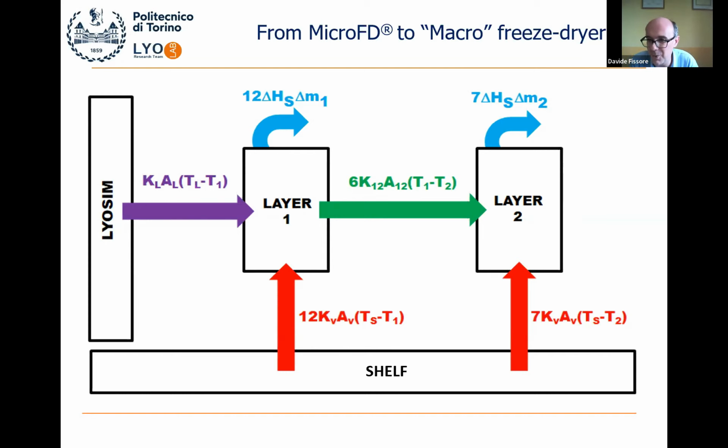It is something similar to the pressurized test, if you have ever carried out one, or have any experience with the pressurized test, MTM, with this type of software and algorithm. In that case, a pressure rise is forced in the machine. Then there is a mathematical model with some unknown parameters, and the values of these parameters are estimated looking for the best fit between calculated and measured values of pressure rise.